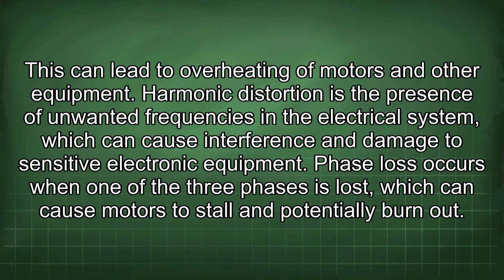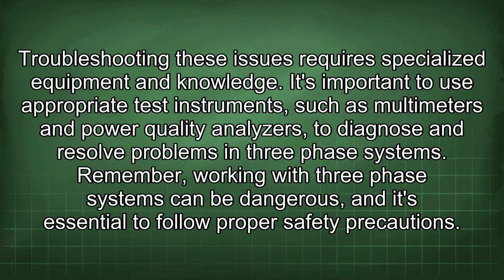Phase loss occurs when one of the three phases is lost, which can cause motors to stall and potentially burn out. Troubleshooting these issues requires specialized equipment and knowledge. It's important to use appropriate test instruments such as multimeters and power quality analyzers to diagnose and resolve problems in three-phase systems. Remember, working with three-phase systems can be dangerous, and it's essential to follow proper safety precautions.